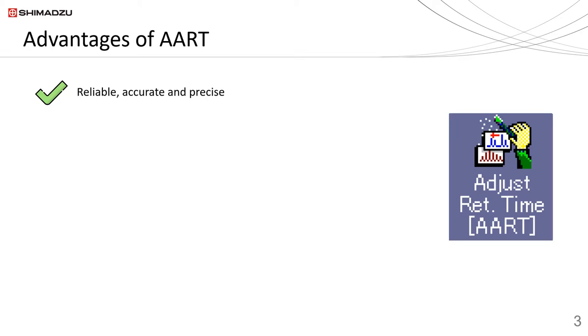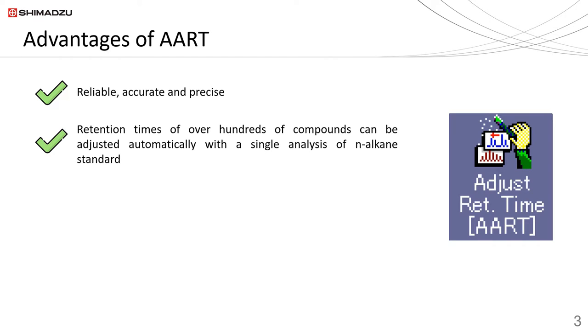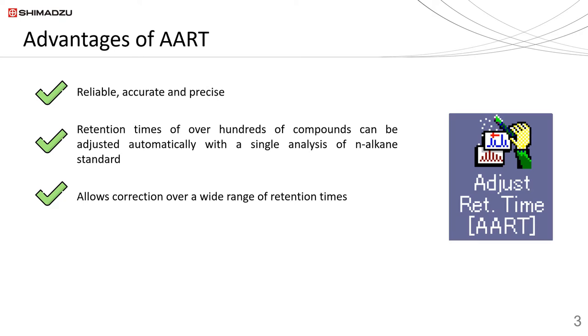What are the benefits of the AART function? Firstly, AART is capable of providing reliable, accurate, and precise calculation and adjustment of retention times. With AART, the retention times of over hundreds of compounds can be adjusted automatically with a single analysis of n-alkane standard, completing retention time adjustment in a short period of time compared to manual adjustment, which requires a few hours. The use of n-alkanes with low to high boiling points also allows corrections at multiple points.